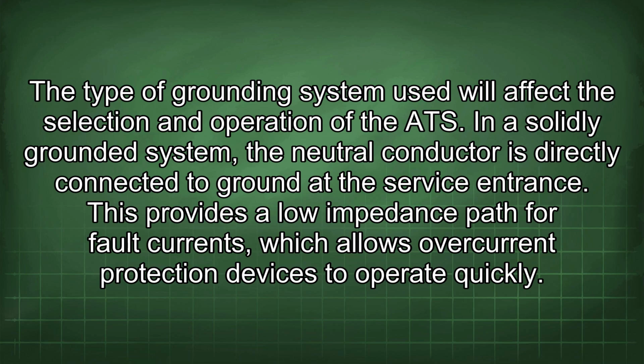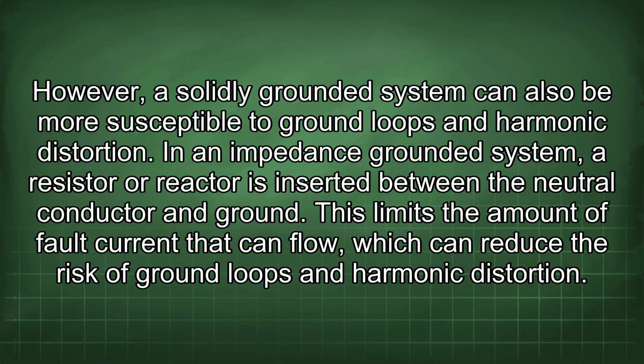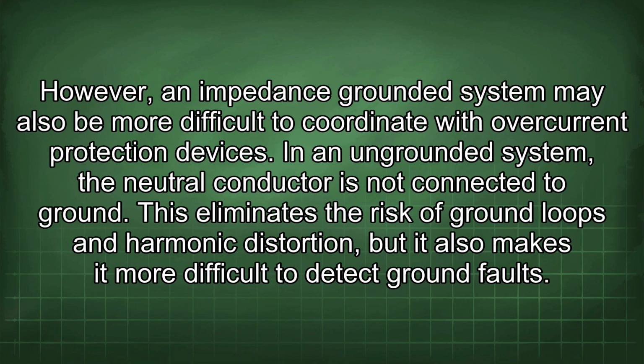In a solidly grounded system, the neutral conductor is directly connected to ground at the service entrance. This provides a low impedance path for fault currents, which allows overcurrent protection devices to operate quickly. However, a solidly grounded system can also be more susceptible to ground loops and harmonic distortion. In an impedance grounded system, a resistor or reactor is inserted between the neutral conductor and ground. This limits the amount of fault current that can flow, which can reduce the risk of ground loops and harmonic distortion. However, an impedance grounded system may also be more difficult to coordinate with overcurrent protection devices.